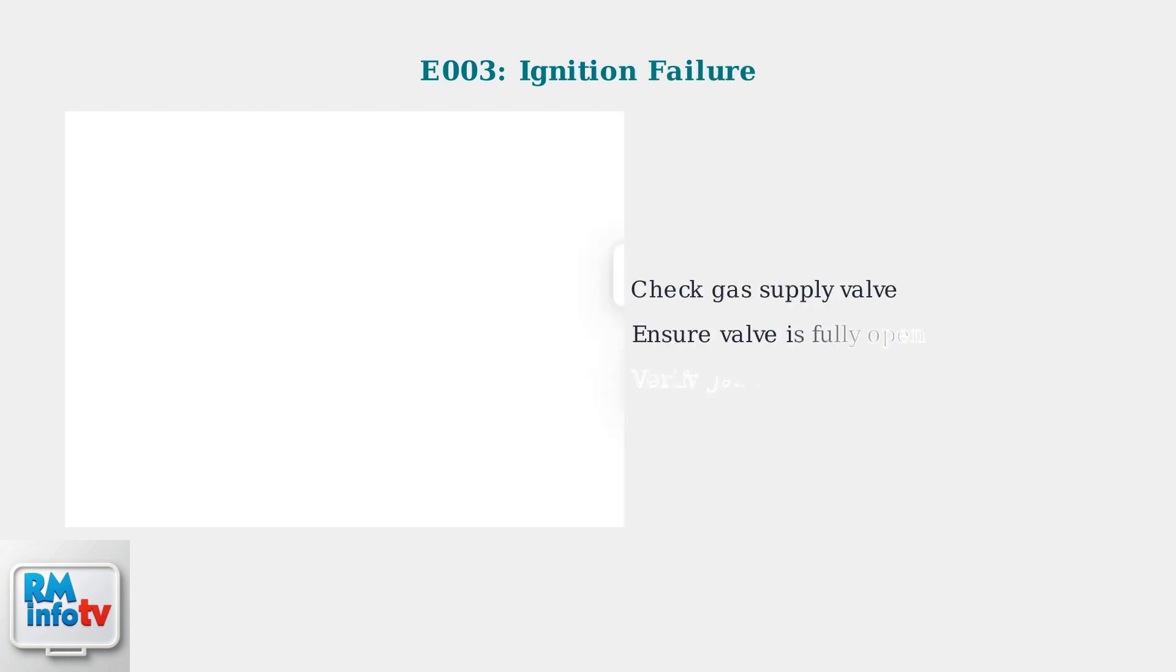Error code E003 indicates ignition failure. This is often caused by a closed gas supply valve. Check that your gas supply valve is fully open before attempting to restart the unit.